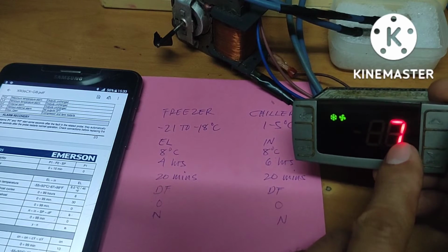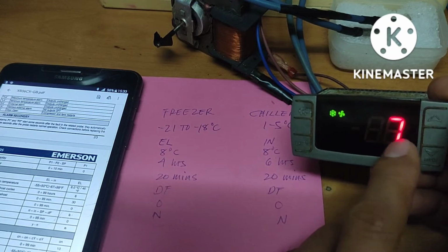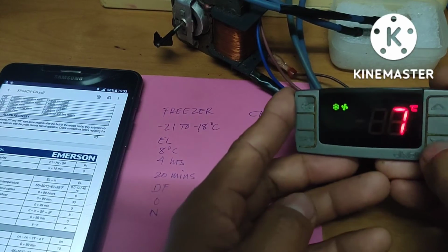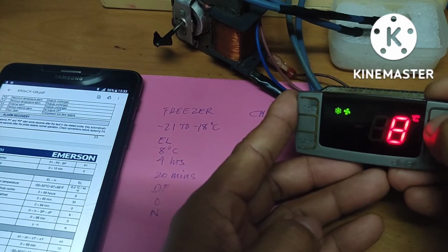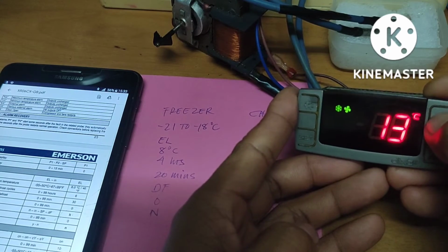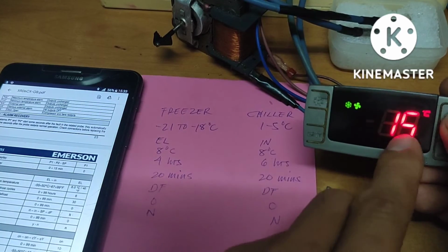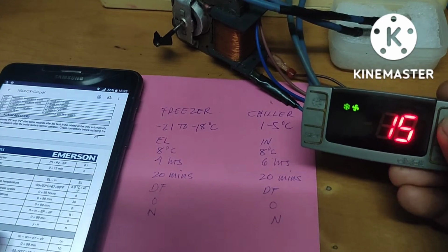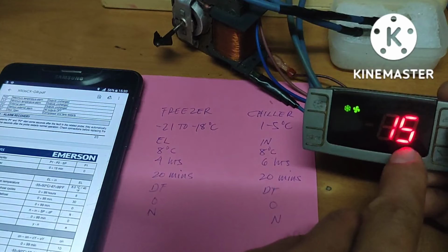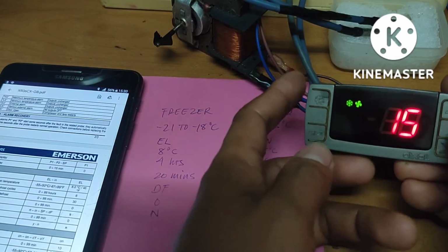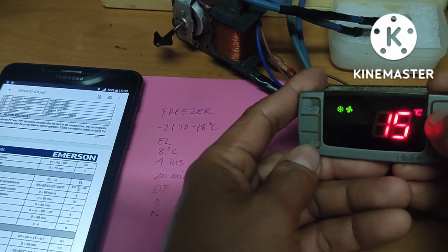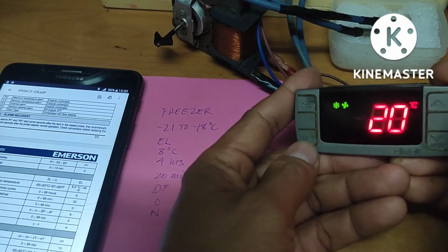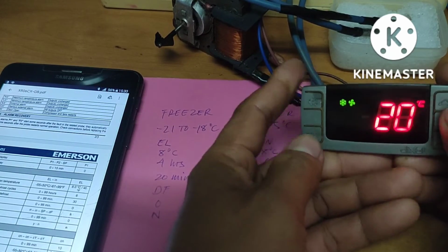This is premature, guys. Do not use 7. Okay, it's being programmed by unlearned people. They set it to 7. The minimum, guys, for defrosting is 15. Regardless of the ID you choose, make your minimum 15 minutes, but ideally just set it to 20, then press set.